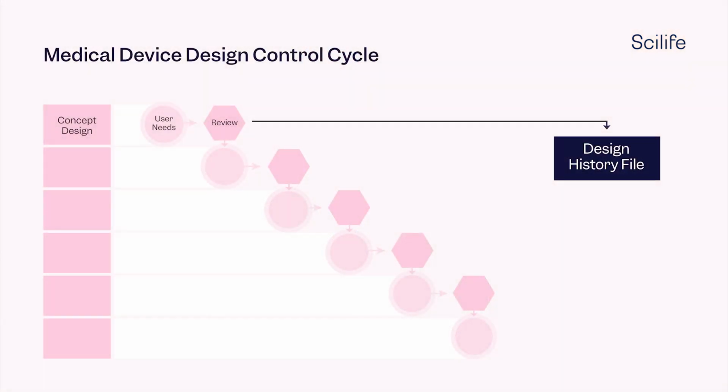The FDA has primarily proposed these steps to be part of the design control procedure. The ISO advice steps are very similar. Manufacturers are required to establish and maintain each of these procedures and adhere to them, although they can add to them if they like. The first step is to determine a few details about the device. For example, your team will have to classify the device, figure out its intended use, the targeted patient population, etc. While this step is carried out before design control or even the design process, how the design control will proceed primarily depends on this step.